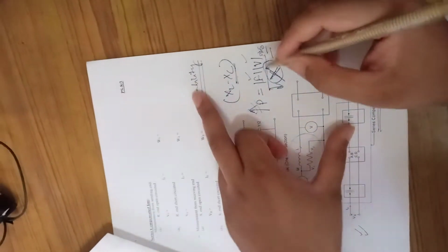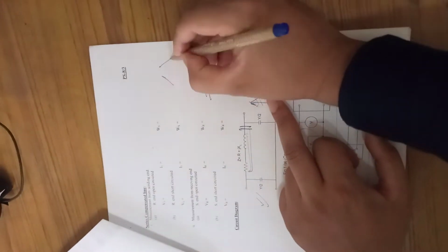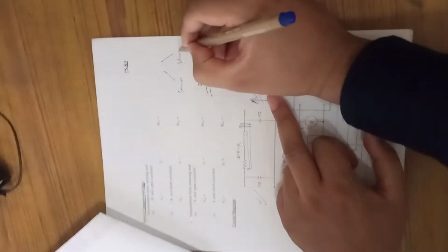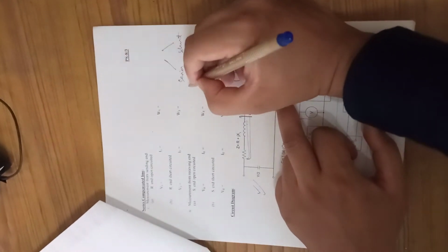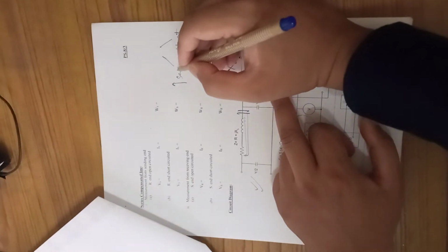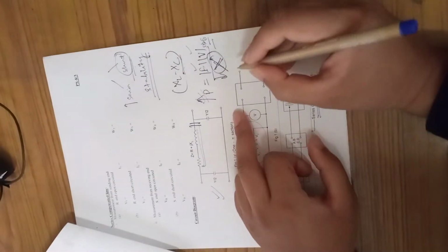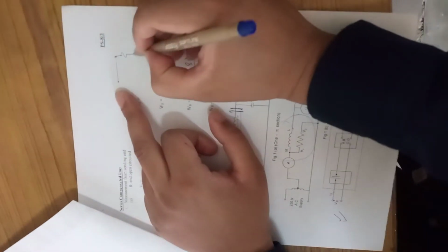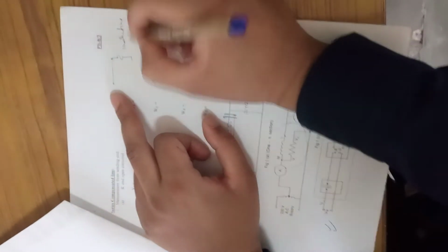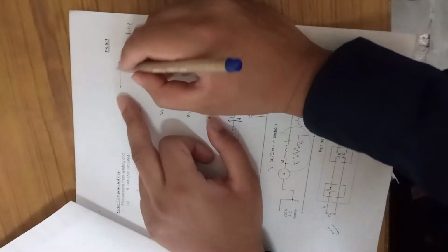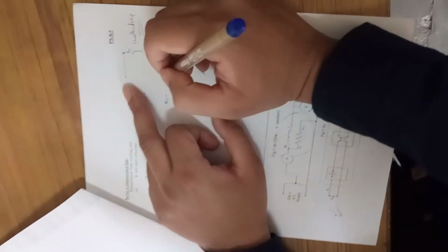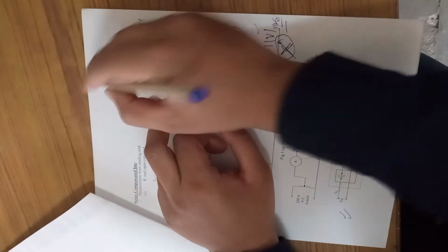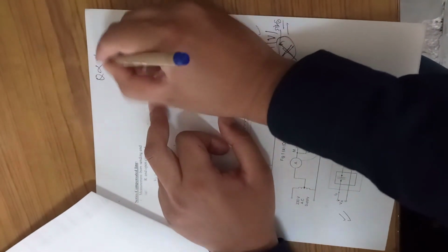And for example, there are two types of compensation. One is series, another is shunt. Series compensation is primarily used to increase the steady state power through the transmission line. Shunt compensation, in which the capacitor is connected in shunt, mostly at the load side, is used to supply reactive power in the system. Because most of the time our loads are inductive in nature, so they require lagging VARs, lagging reactive power, from the system. And Q, you know from your load flow studies, is proportional to V.